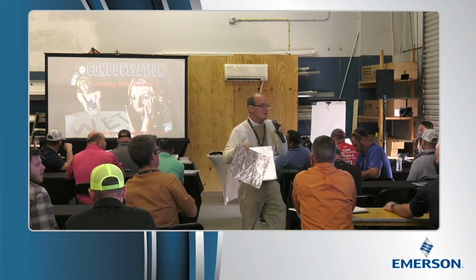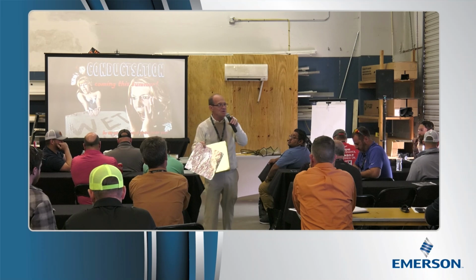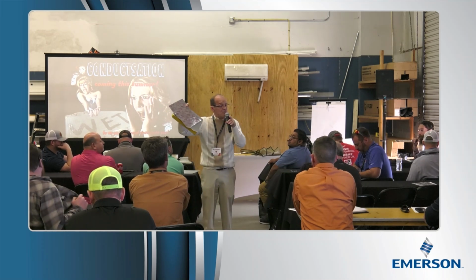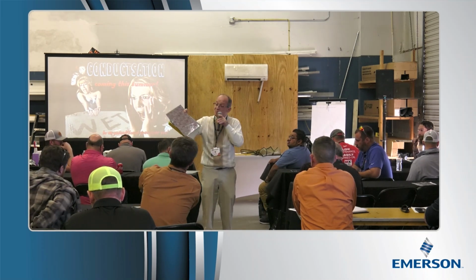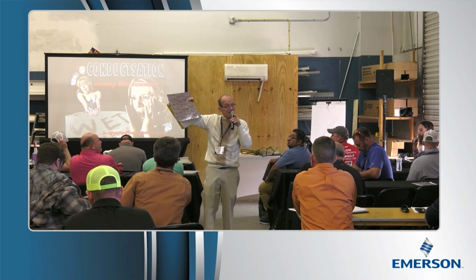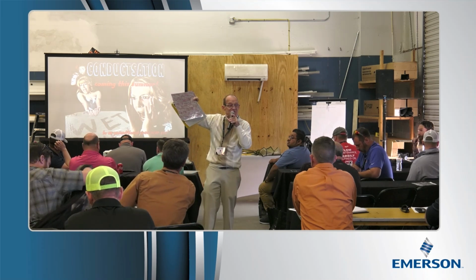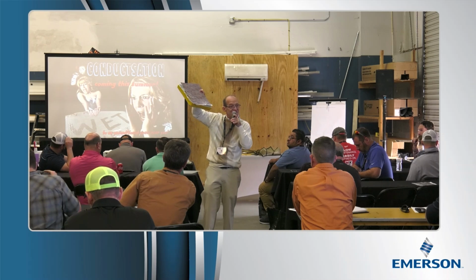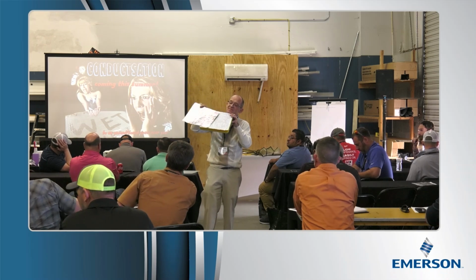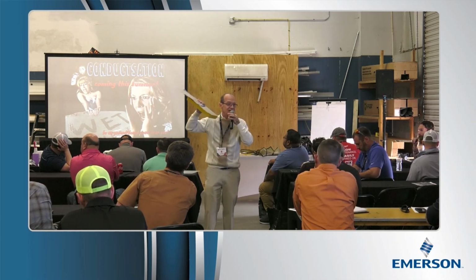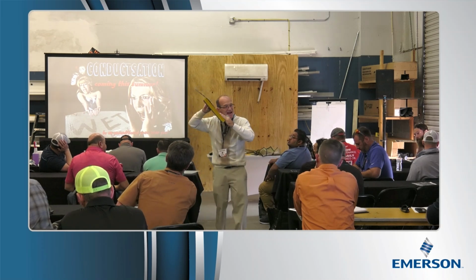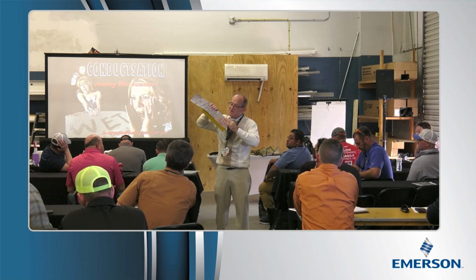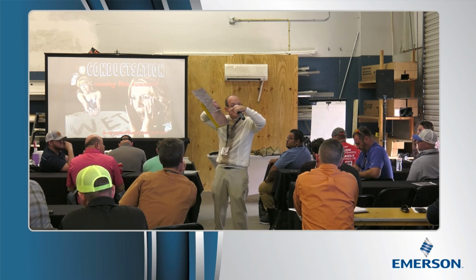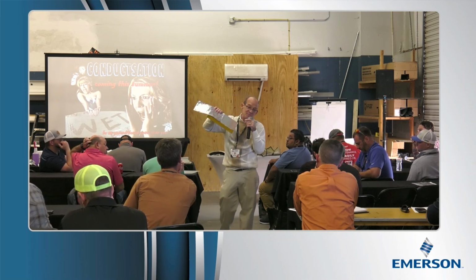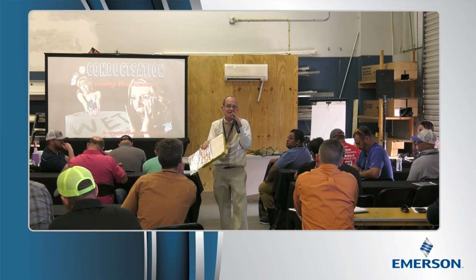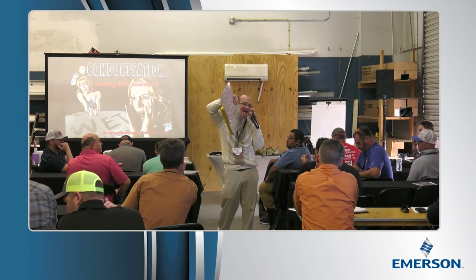You'll notice if you go look at wet duct systems and troubleshoot them, the beads of moisture people see will be on the taped part because it's not permeable. The water molecules condense on the surface of the tape. Right next to it, there's no visible sweat on the ductwork, it's just damp to the touch. But that has the same amount of molecules, it's just sitting on top in one case and absorbed into the other. So a lot of times when people see tape spots, they think that's where it's sweating. Well, no, it's sweating over the whole thing. That's just where it can't absorb.